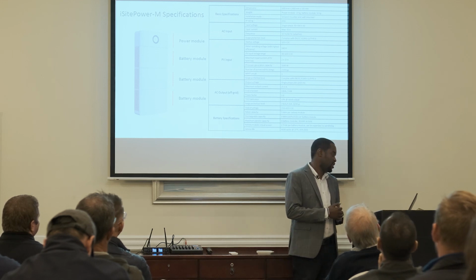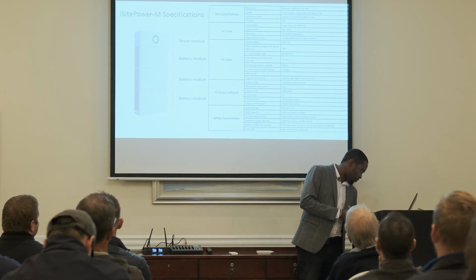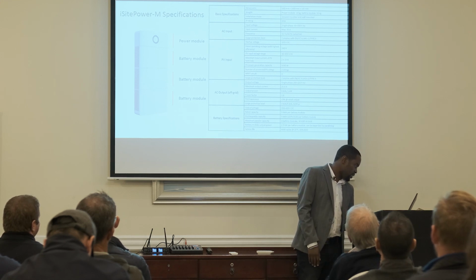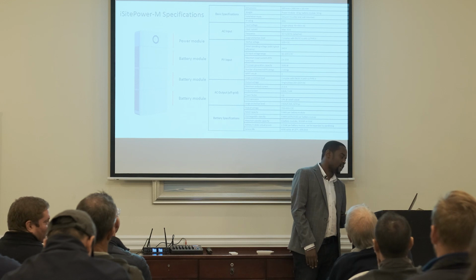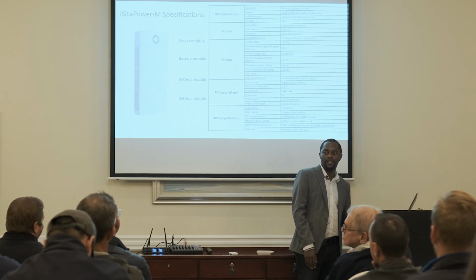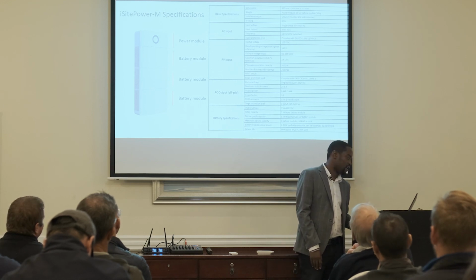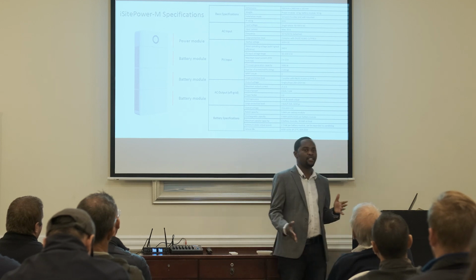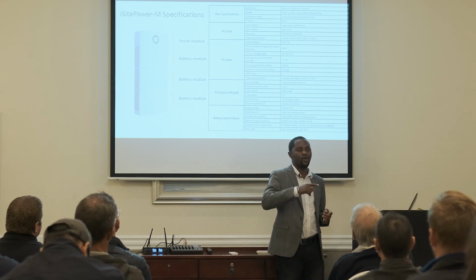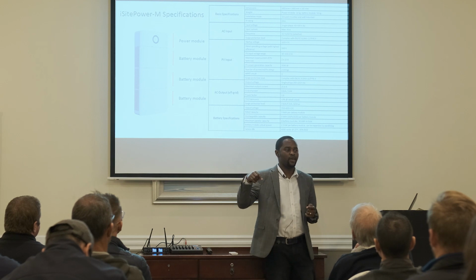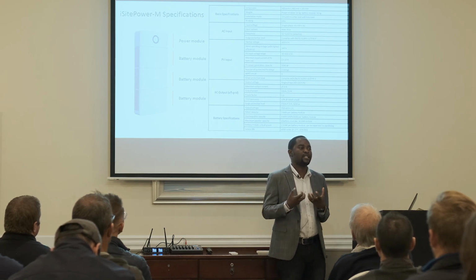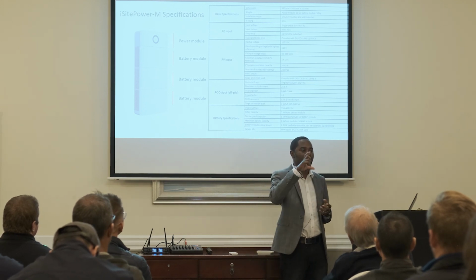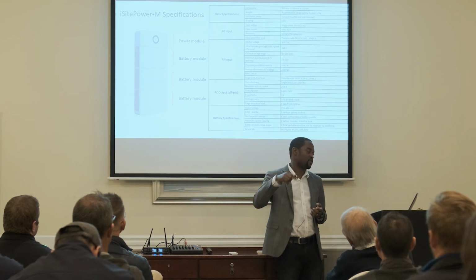You have got the AC grid input, and it operates at 0.833 power factor, right? I also realize that when you've got grid, the inverter is riding on the grid, so your sine wave is more pure. Then when you lose grid, the inverter generates its own reference, so there's bound to be some distortion in the purity of your sine wave.